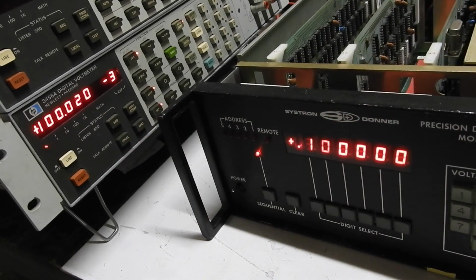Go to the 10 volt range. 1 volt, correct. 100 volt range. 10 volts, correct. Now here's the test. 1000 volt range. Puts it in standby. Now we take it out of standby, we should get 100 volts. Bloody close. That could be it.